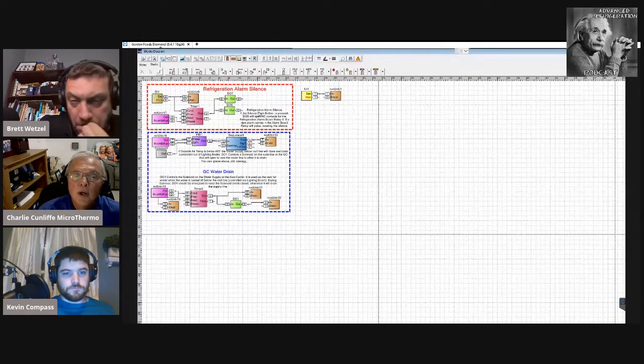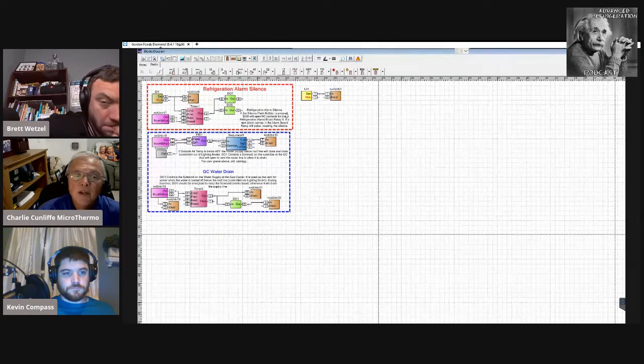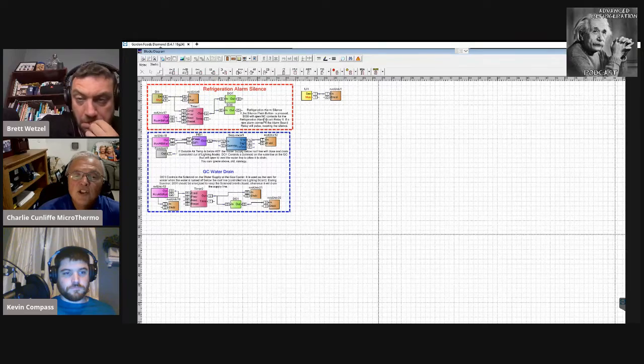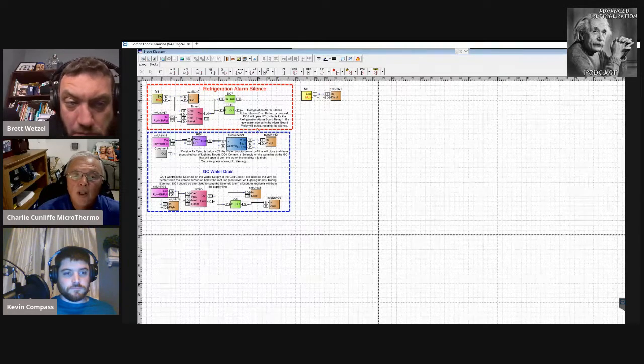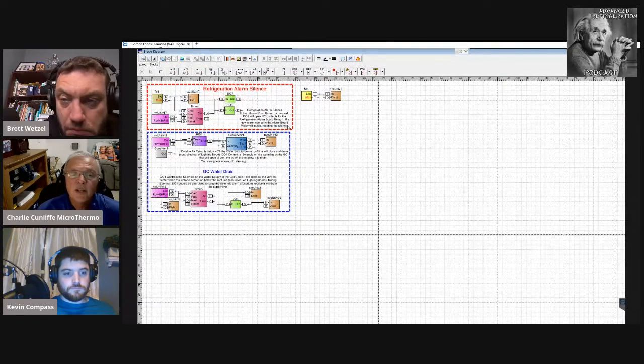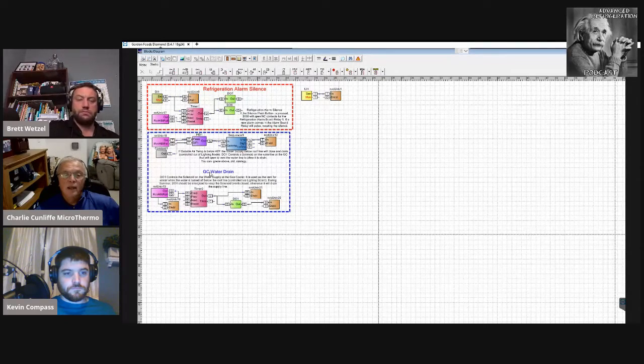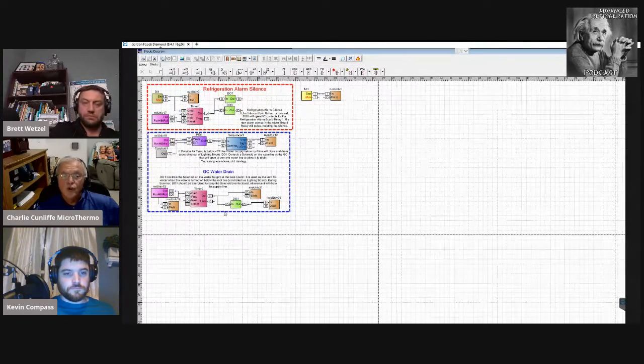He did a good job here. Alarm silence: if the button is pressed, DO8 will open NC contacts for the refrigeration alarm board relay number one. If a new alarm comes in, the board relay will pulse and reset the silence. And here's a gas cooler water drain.